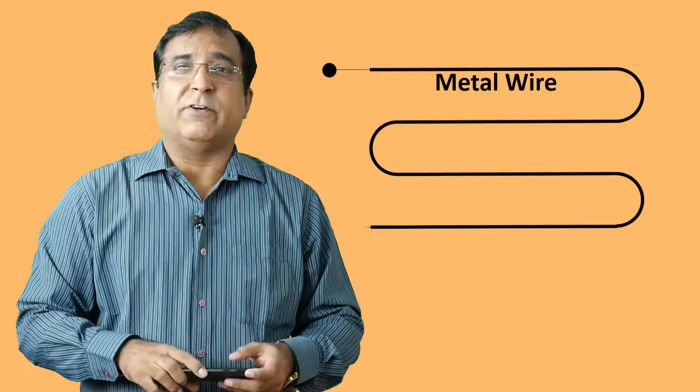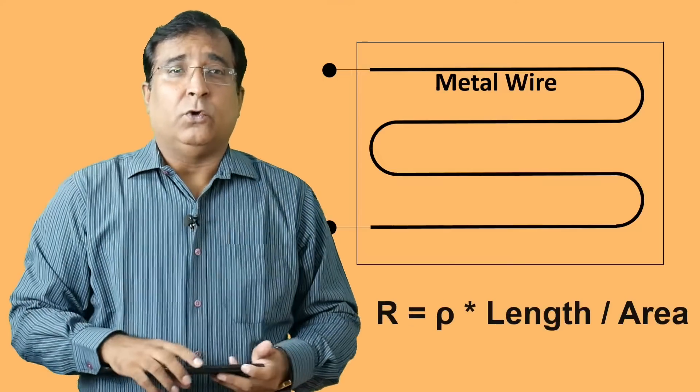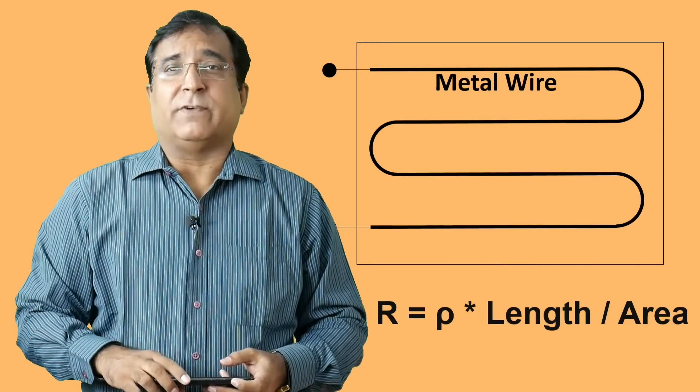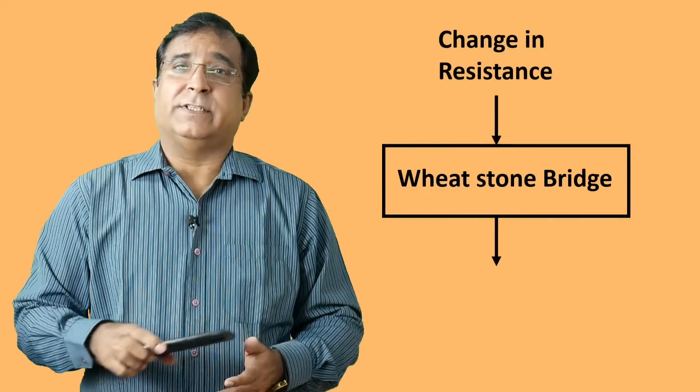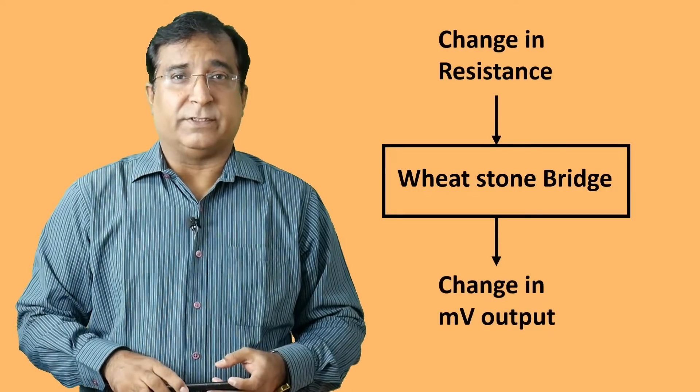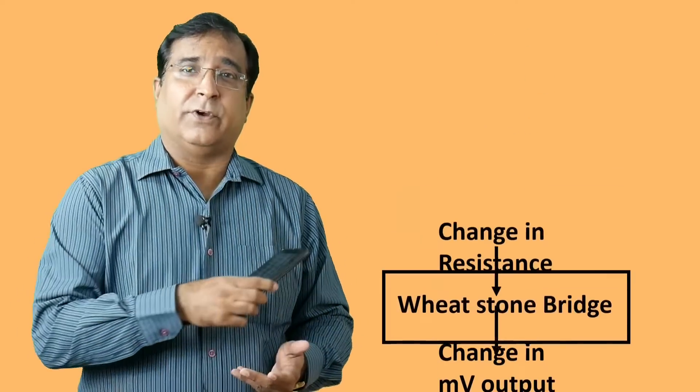The resistance of this wire is governed by this formula. So when an external force is applied to this wire its length or area gets changed. This causes its resistance to change. Now we can measure this resistance change with the help of a Wheatstone bridge as can show in terms of millivolts and also we can show in terms of kilograms or tons.